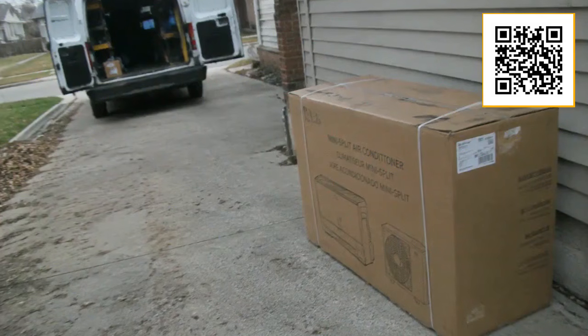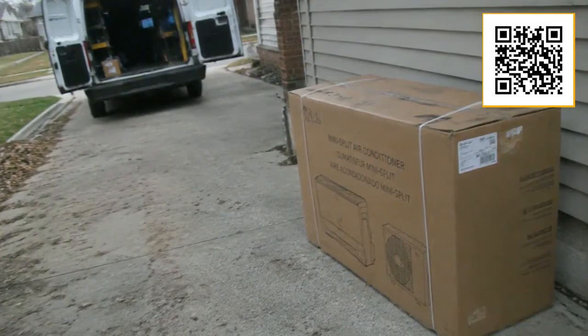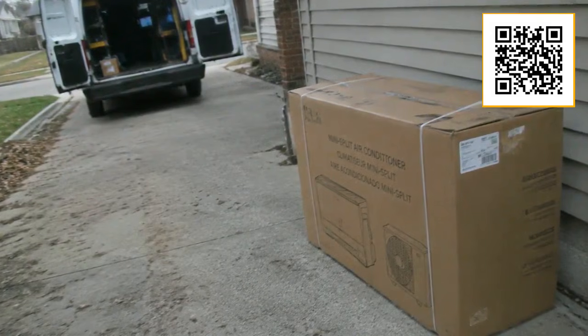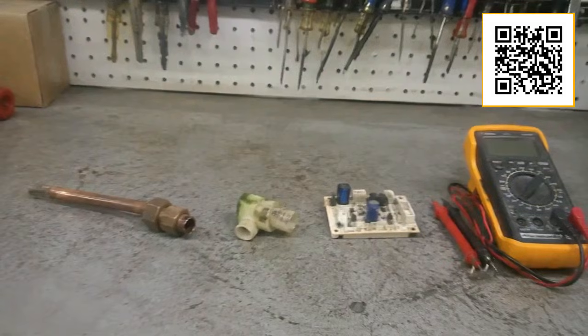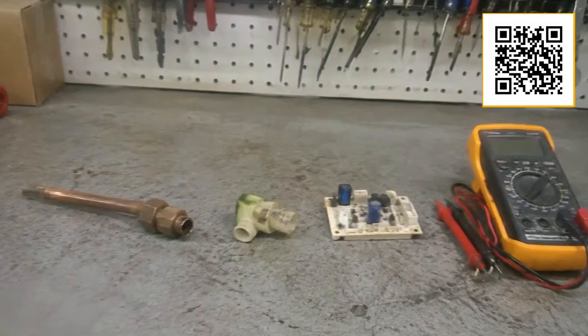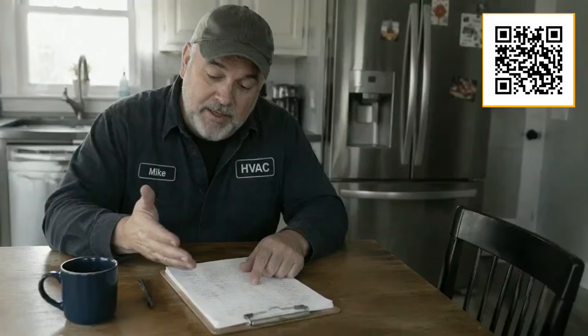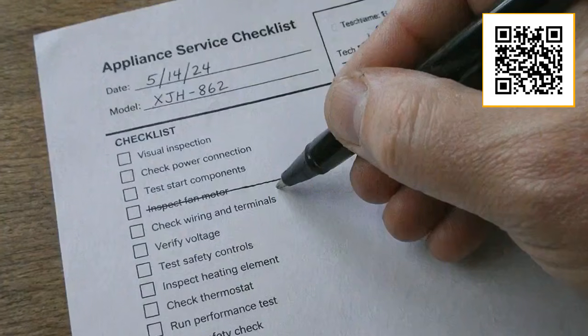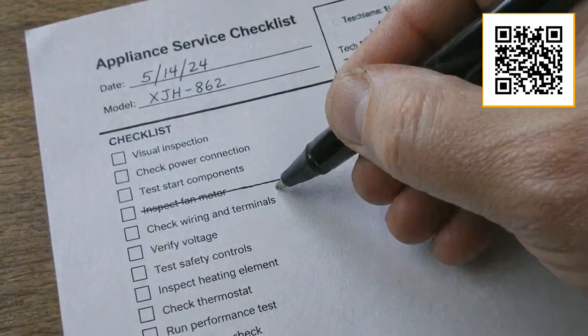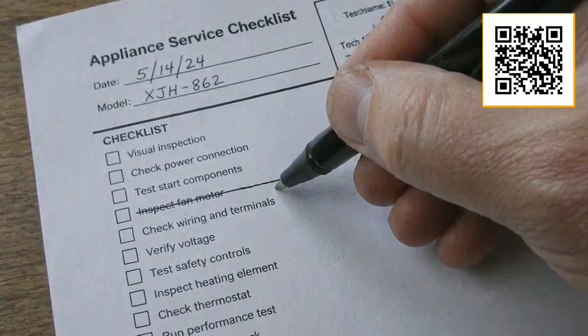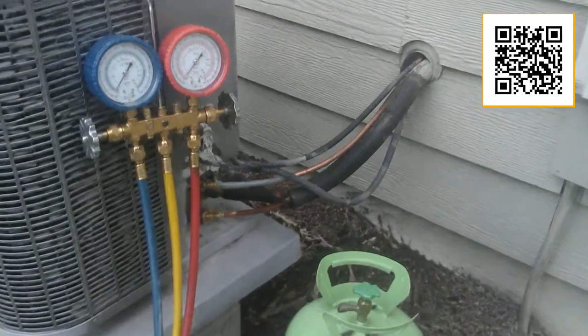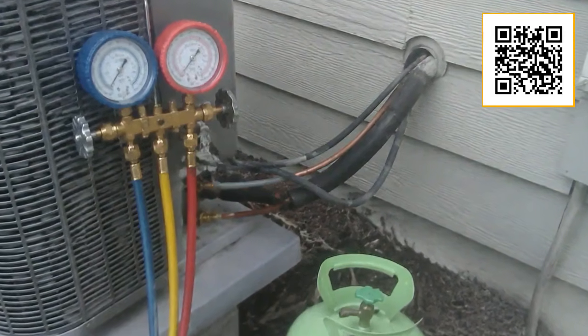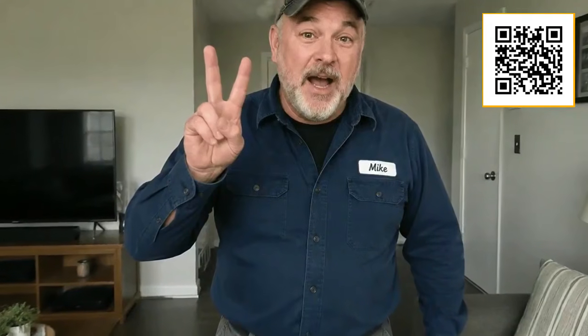Some folks buy mini splits through online retailers and hire whoever is cheapest to install them, and that combination tends to produce problems down the road. A good mini split installation is not complicated, but it requires care and experience. If you are considering one, ask the installer specifically about their experience with that brand and whether they will pressure test the refrigerant lines before startup. Those two questions will tell you a lot.